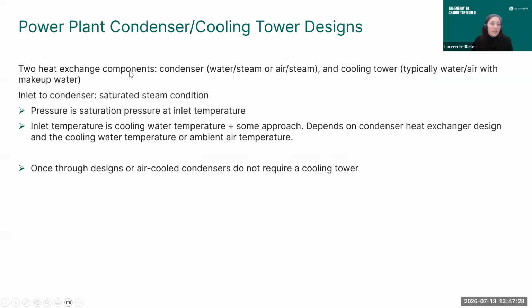So when you consider designing a power plant and what kind of condenser you're going to use, there are a few different things to take into account. First of all, what kind of heat exchanger are you going to be using? What is your cooling source? As we just discussed, you can either only use air or you can use water, and typically that is paired with air, so there's typically an air element involved. For the condenser itself, the inlet condition is typically saturated steam. You want the temperature at the outlet of the steam turbine to be as low temperature and pressure as possible because that indicates that you've extracted the most energy. If your pressure is higher, if your temperature is higher, that means that there's less energy that has been extracted and is still remaining in your gas stream. So for the sake of the discussions today, we will assume that the inlet conditions for the condenser is saturated.